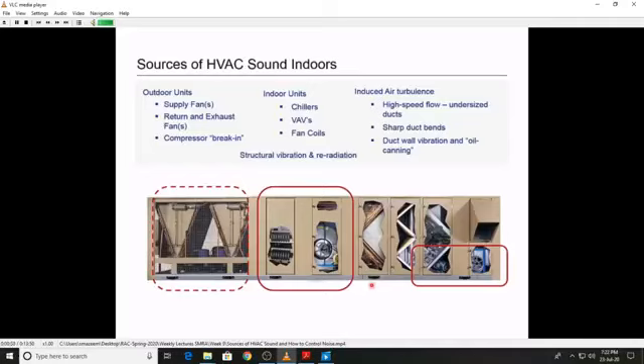Noise can be induced by air turbulence, and this is particularly a problem with high-speed flow and undersized ducts. Likewise, very sharp duct bends also generate a great deal of turbulence that can turn into noise. And if the turbulence is low enough in frequency or pulsation rate, then it can induce actual duct wall vibration or oil canning. And finally, there are many paths by which the structures can vibrate and then re-radiate the sound indoors.